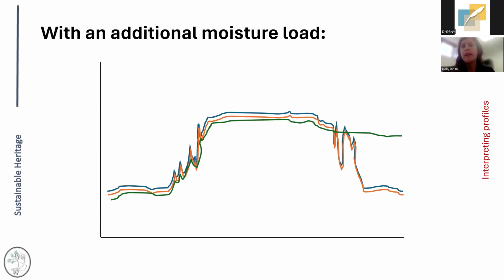This is kind of a more extreme example, but again, if you have data from multiple spaces, you might see a moisture load. You can see here, in this instance, green was following right along with the blue and the orange. If I saw the data from mid-year back, I'd probably say, oh yeah, these are served by the same spaces. But towards the end of the year, blue and orange drop down and green is still maintaining a level. So obviously it didn't switch which air handler was serving it, but it could indicate that there's a moisture load present within that space that's preventing it from dropping down.